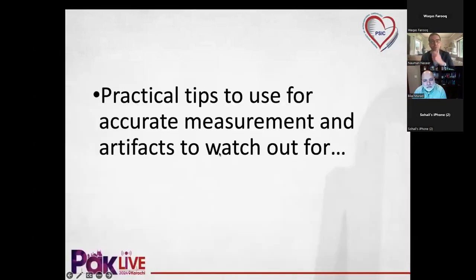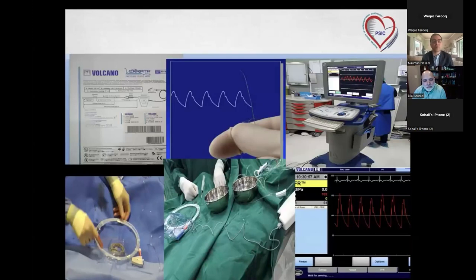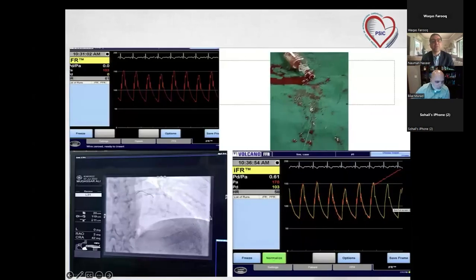Now, practical tips to do the measurements and the artifacts to watch out for. This is set up in my lab. The pictures are from there. This is the 0.014 wire, and you just take it out from the packet, and I flush this ring in which the wire is placed. Let it sit for 30 seconds. Then I hand over this wire to be plugged in over here. Once you plug it in, automatically it says wait for zeroing over here. And this is the console in the lab on which it's saying wait for zeroing. And once it's zeroed, then it says ready to insert.